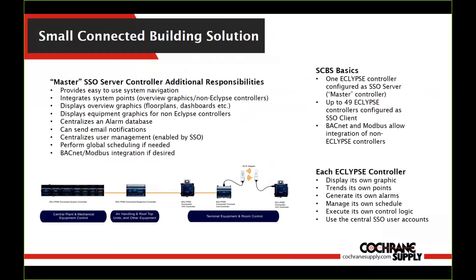The master controller creates the interface that makes everything feel like a single system, even though it's distributed. Your navigation lives in that one controller. It pulls in points for overview graphics and displays those overview graphics. It pulls in the remote web graphics server from each controller embedded into the interface. You can have it report alarms from the other controllers, push those alarms via email notification or email to SMS. You only have to manage one user database — it lives in that master controller and passes authentication throughout the system. You can create a main schedule in the main controller and pass that information through, and pull in BACnet or Modbus points into that controller as needed.